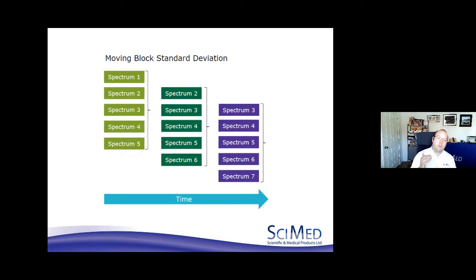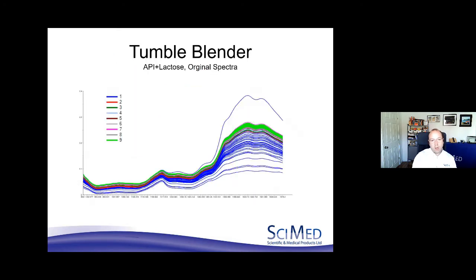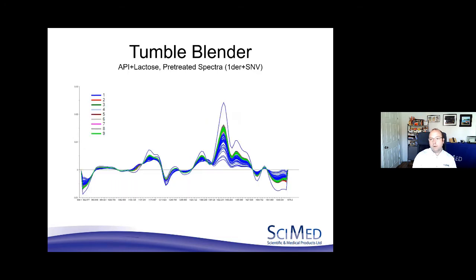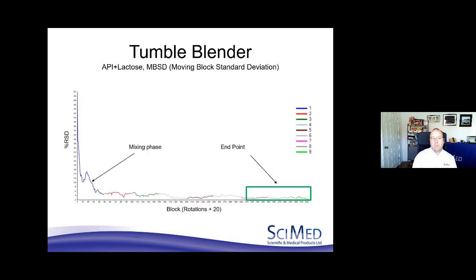So we compare the spectra 1 to 5, then we compare the spectra 2 to 6 and 3 to 7 and so on. This is the raw data from just a typical blend. And you can see that the green line there is the convergence of the NIR spectra as the blending proceeds. Quite often we do some pre-treatment of the data, in this case being an SNV and a first derivative. And then when we plot the moving block standard deviation, you see the initial mixing stage, followed by hopefully at some point a nice steady state, and we can define the endpoint.